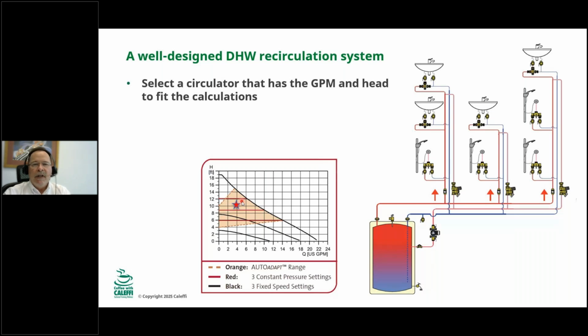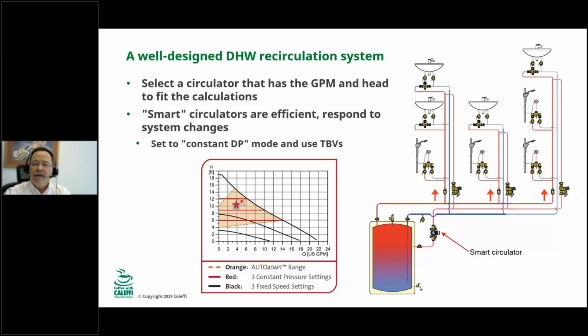Yep, good lead in. So smart circulators are the way to go. We certainly believe so because they respond to system changes like Max just said. If you had a smart circulator set to constant differential pressure mode and you're using thermostatic balancing valves, to me that's a perfect marriage. The thermostatic balancing valves modulate, opening and closing, so they're the only kind of balancing valves that actually change the GPM as the system dynamically balances. They control temperature, and as they do their job, a smart pump set to constant differential pressure mode will ramp up and ramp down to maintain the required head in the system to get the right flow. So they go together very well.